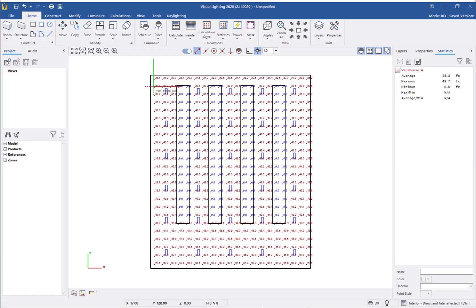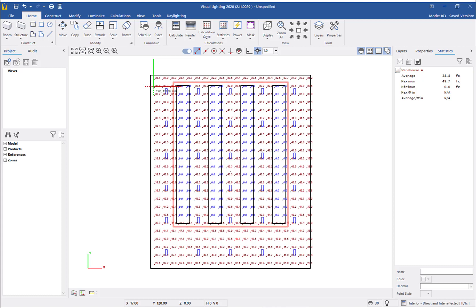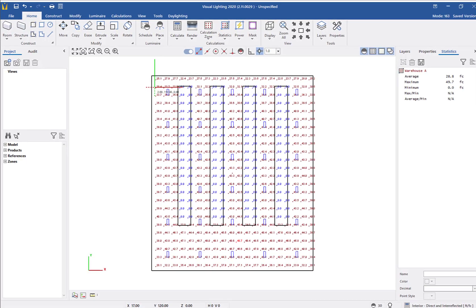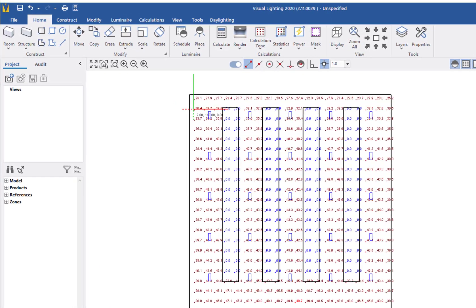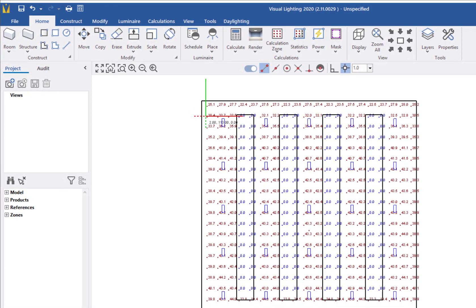At this point, I can see we have a problem, as the racks are covering up some of the calculation points and it's producing zero foot candles which affects the results. The solution is to mask these calculation points under the racks.